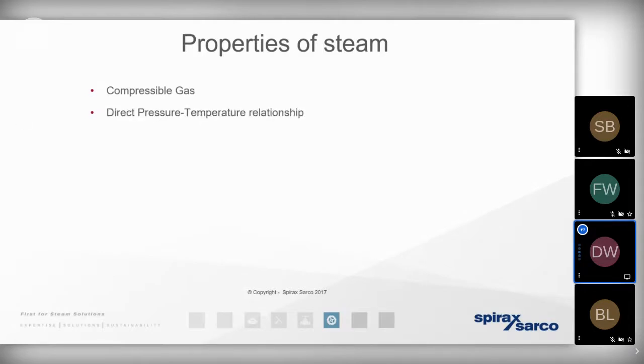We also know that we've got that direct pressure to temperature relationship that we've spoken about. By controlling the pressure, we're manipulating the temperature. High pressure steam has got a high temperature, a lower pressure steam has got a lower temperature. So you remember that that makes it very, very easy to control the temperature of the steam at the process using a very simple two-port valve. We've mentioned that there's a considerable amount of heat energy present in a kilogram of steam compared to a kilogram of water, up to 50 times more energy present in a kilogram of steam compared to LTHW that could be working on an 11 degree delta T.